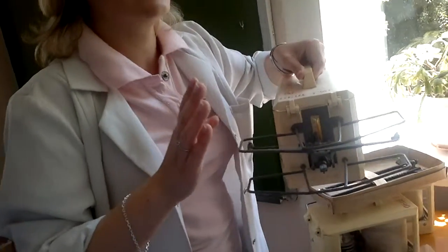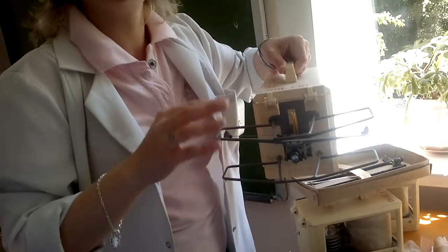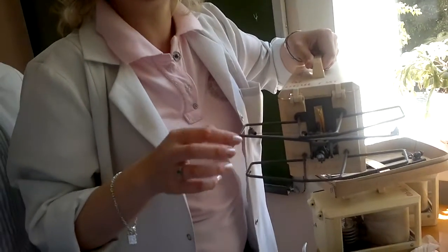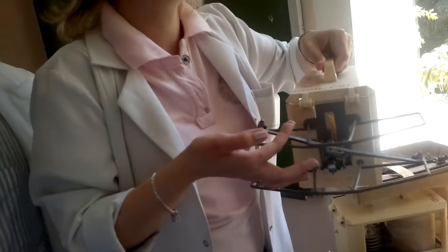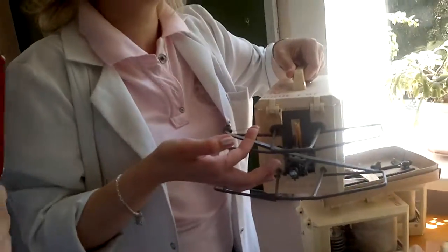Hygrograph. Listen, if you see that in the name of appliance is hygro, it's for relative humidity only. If psychro, for absolute and maximum humidity also. Sensitive element, horsehair, it will increase or decrease its length dependently on water steam concentration in the air.